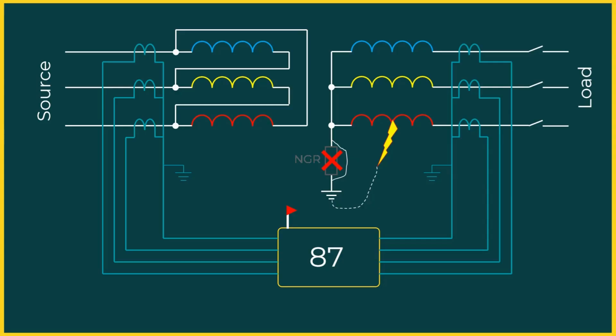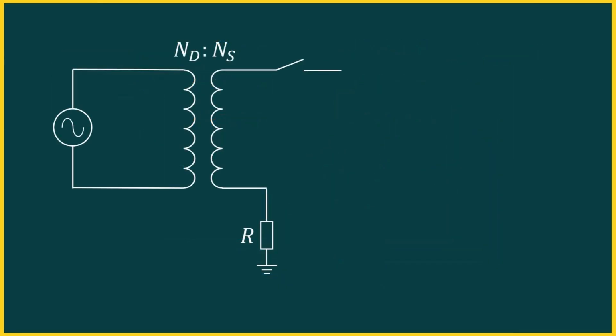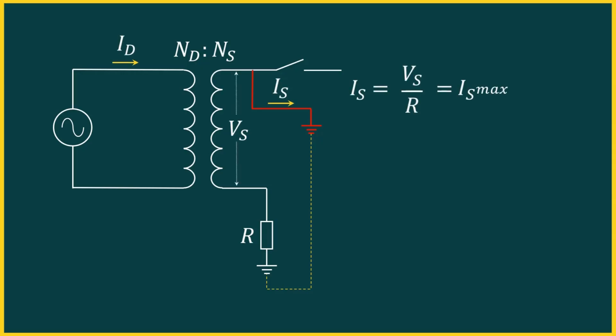To understand this, we need to revisit how fault currents behave in a delta star transformer. Let us consider a single phase arrangement. Imagine an earth fault occurs at the winding terminal. The voltage behind the fault is Vs, and hence the star side current will be Vs upon R, where R is the NGR ohmic value.